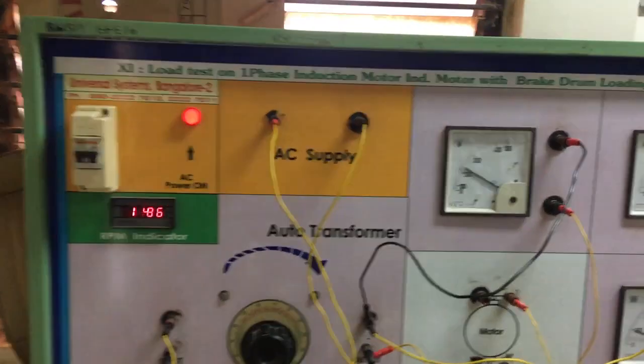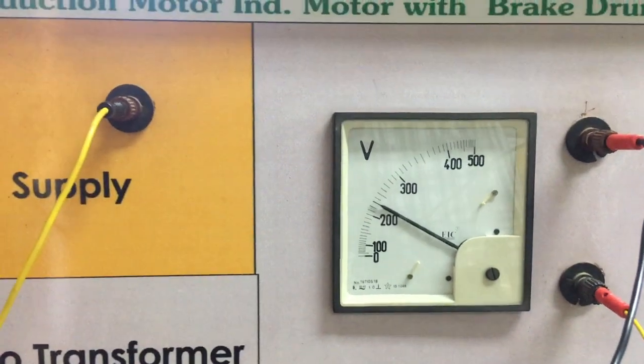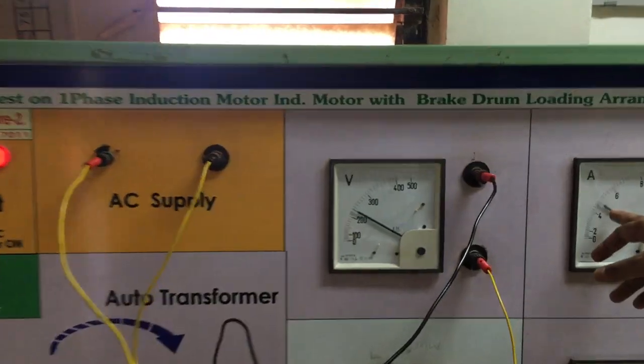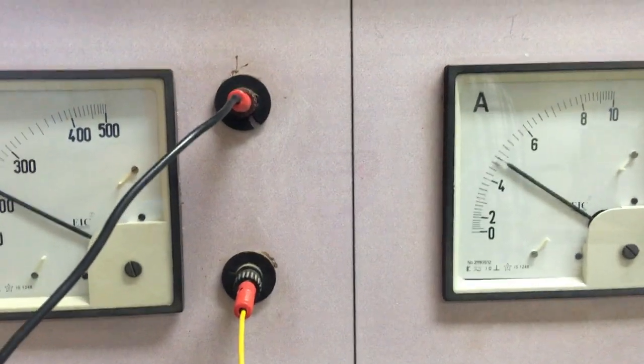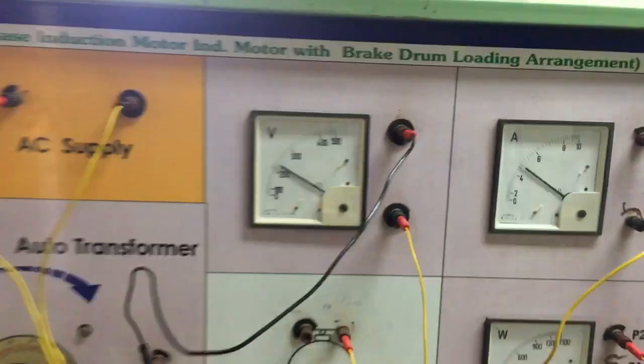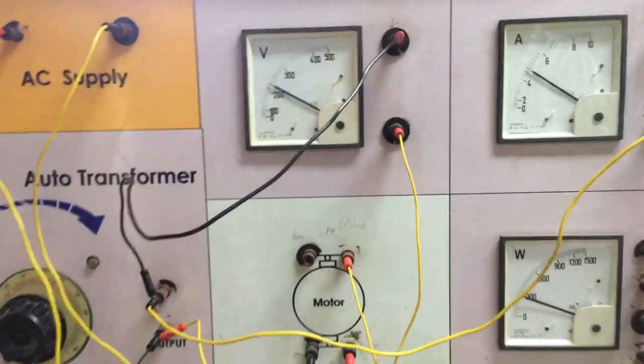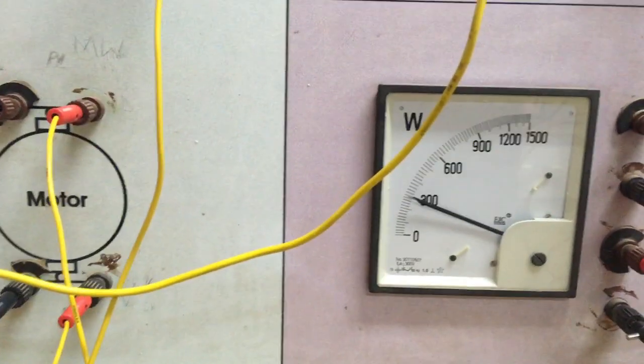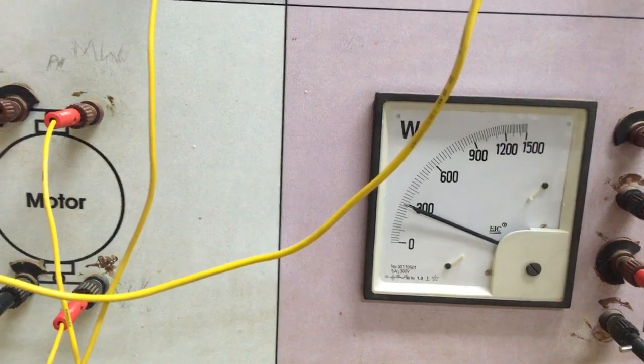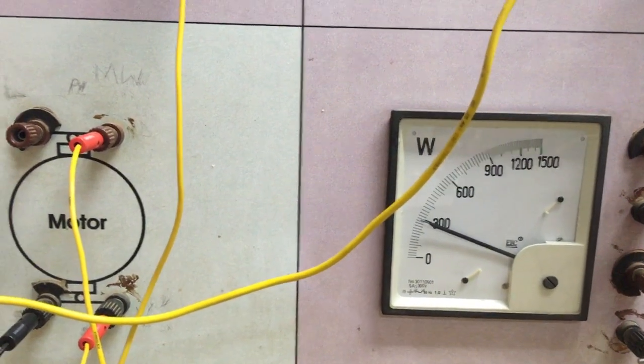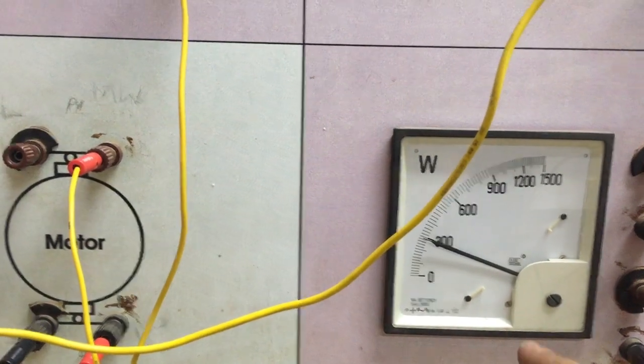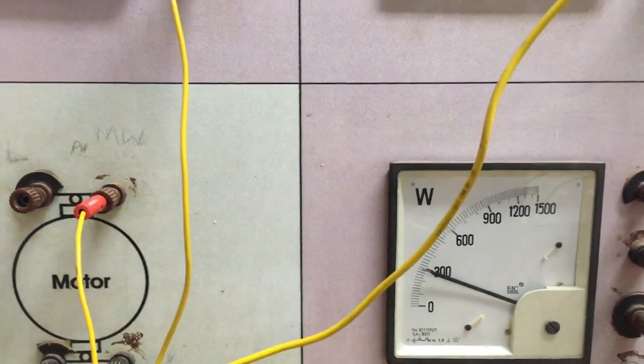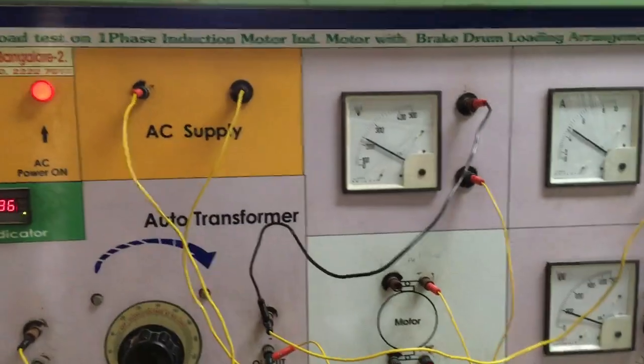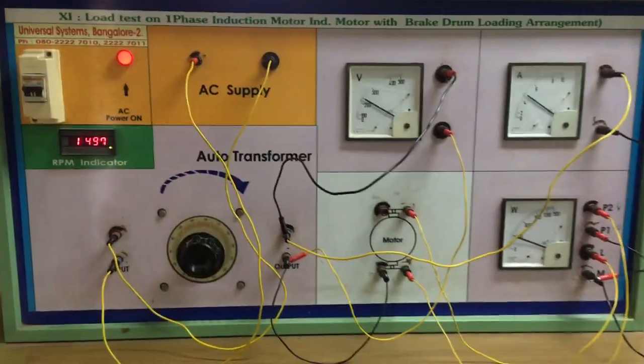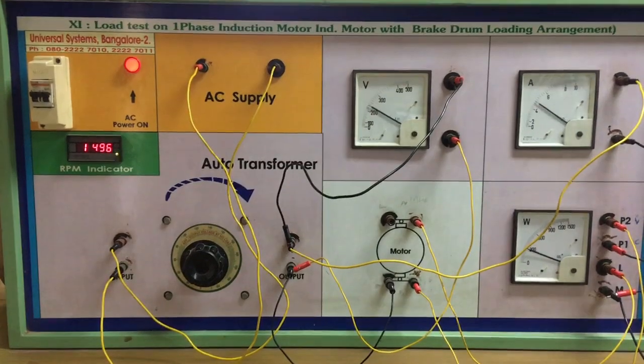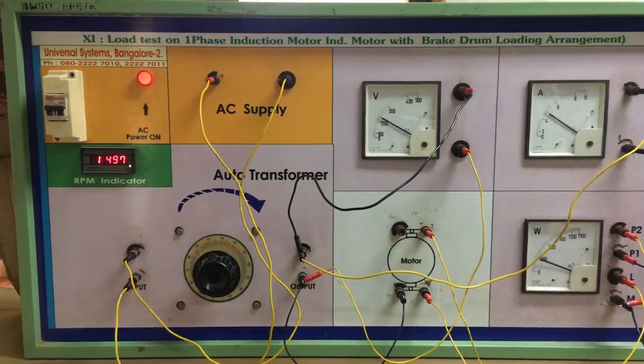I have varied the input voltage using the auto transformer to 230 volts, and observe the no load current is around 4.4 amperes. The full load current is 4.6 amperes, but the no load current itself is 4.4 amperes. I told you that motors will draw large no load currents to overcome the rotational losses and iron losses. The power drawn at the no load condition is nothing but the entire loss. It is the no load copper loss plus rotational loss plus iron loss. So the wattage is around 300 watts, so the losses in the motor I can take as approximately 300 watts.